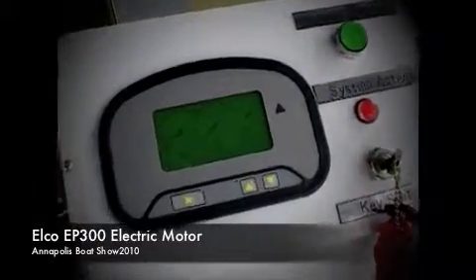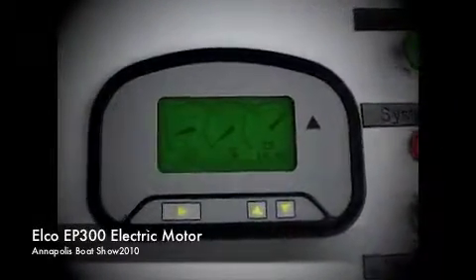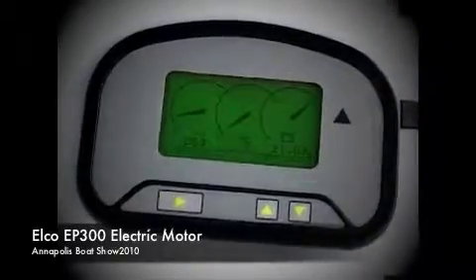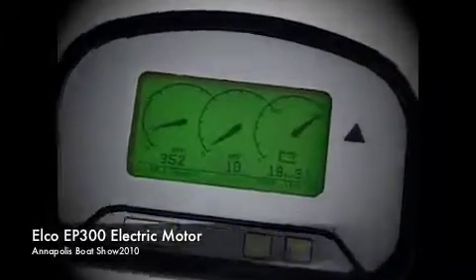This motor is totally enclosed, unventilated. It can run submerged for periods of time. Water can splash on it and it won't stop the motor. With historically the DC motors, if they got wet, the commutators would spark and conceivably burn out.